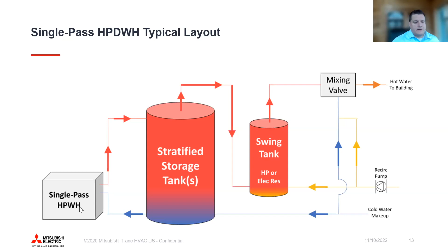The purpose is really to make sure when we have our recirc loop from the building coming back, let's say our mixing valve is sending out 120-degree water, our recirc is coming back at 110. We want that to hit the swing tank first, so that's the tank that's moving around in temperature, not our storage tanks. If we were to bring back that recirc right to the storage tank, we would mix it all up, and essentially we would get a higher entering water temp to our heat pump, which would sacrifice efficiency. So there are a little bit more added steps to designing for a single pass system, but your ultimate end game is a lot better performance and higher efficiency, especially in colder climates.